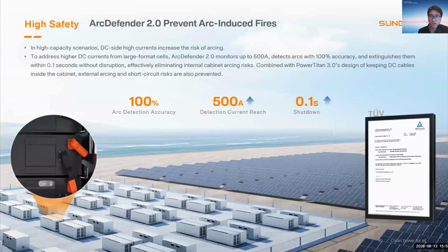And another major safety risk in high-power DC systems is arc fault. With larger cells, the DC current is much higher, and this makes arc detection much more difficult. So our Arc Defender technology features more sensitive current sensors and a smarter AI algorithm. So even when the DC current reaches 500 amperes, the system can still achieve 100% detection accuracy with zero missed detection. At the same time, the arc extinguishing speed is more rapid, and the risk can be cut off within just 0.1 seconds, which can significantly improve the system reliability.